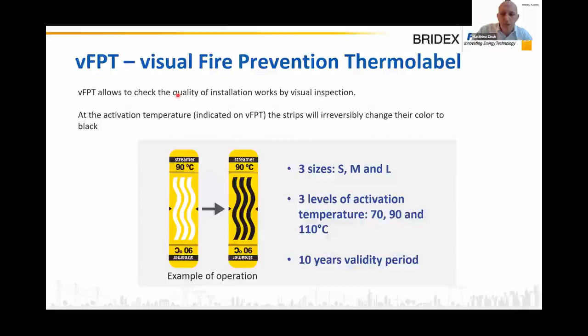We have another type of sticker that is basically a visual sticker, and it contains no gas. It's only meant for showing you, like the thermodots, whenever you have crossed a threshold of temperature. They come in different sizes as well, S, M, and L, according to the conductor size. And they have different levels of temperature activation. Some of our customers use them for capacitor banks, for example, with a lower temperature, like 70 degrees. They have 10 years of validity, and we have a series as well that can be used outdoors.